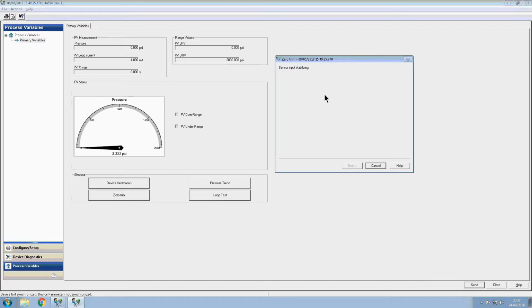The input will try to stabilize and check if the value is within the allowable zero range. If it is found OK, it will be applied as the new sensor zero and the screen will say that the method is successful. If the new value is not found to be OK, then the screen will display an appropriate message for the user, for example, the value is too high. After the calibration is successful, the device may be returned to automatic control. Press Finish to acknowledge the completion of the method.